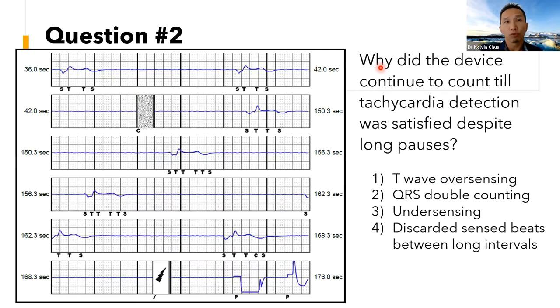So question number two is, why did the device continue to count until the tachycardia detection was satisfied? You can see on this S-ICD strip that there were kind of long pauses. My question is, shouldn't the device have stopped counting and stopped tachy detection? So why did the device continue to count until tachy detection was satisfied and delivered the shock? Was this due to T wave oversensing, QRS double counting, undersensing, or discarded sense beats between long intervals?